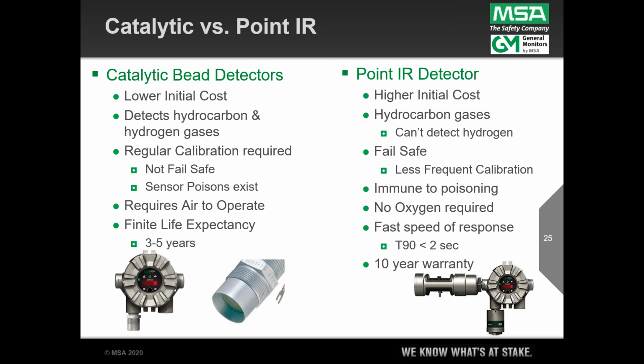But let me say one thing. Regardless of technology, cat bead or point IR, the technicians on site responsible for managing the system need to do a visual walkthrough, because if the gas path is blocked from something external, and at one site I went to, the painters had left bread bags taped around the gas detector. No instrument, regardless of manufacturer, is going to be able to sense that I've got a piece of tape or a bread bag wrapped around the instrument. So it's that visual check. Just like I talked about flame detection, it's the same thing here. We have the same: green is good, red is alarm, yellow is trouble. So part of that daily walkabout is to look for the green LEDs on all your gas detectors, and make sure there's not a bread bag wrapped around the instrument.